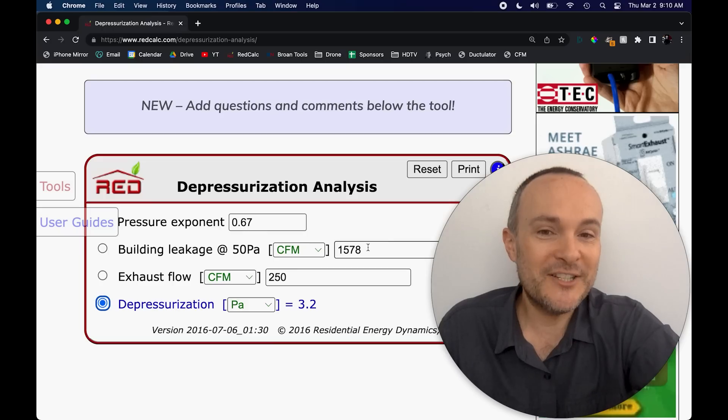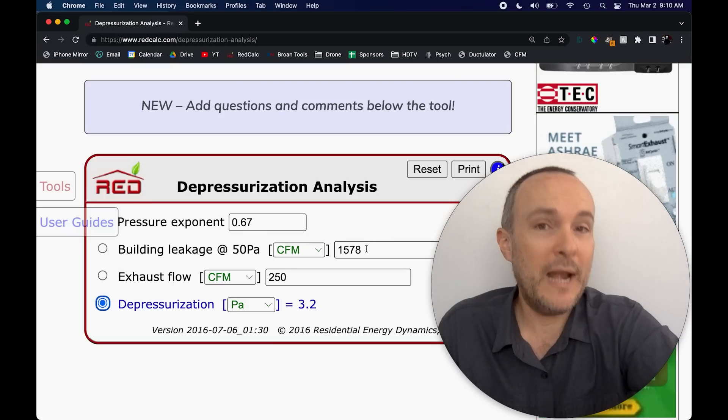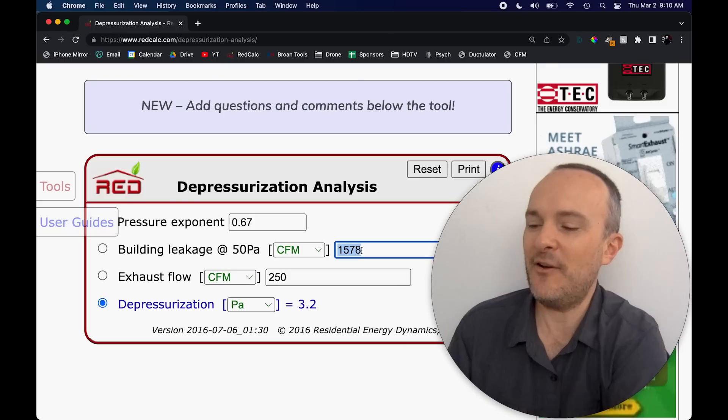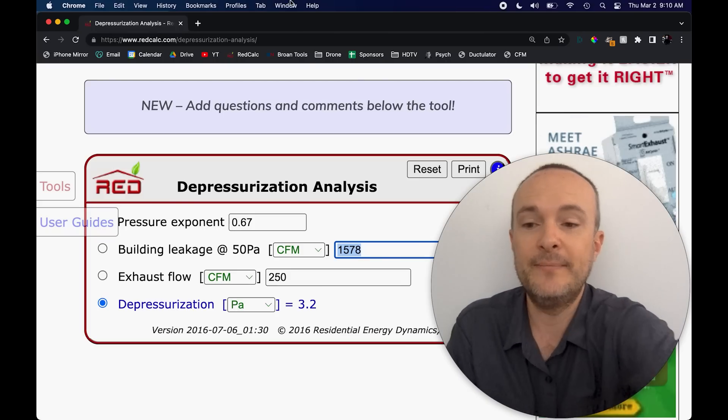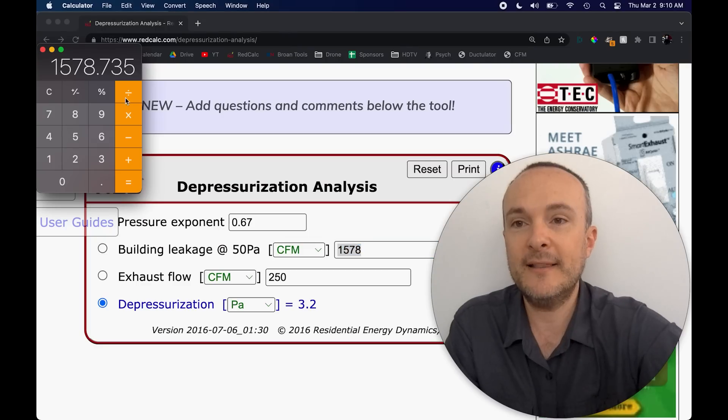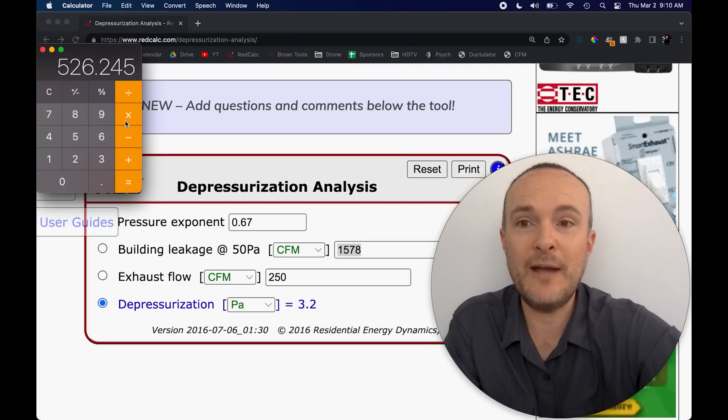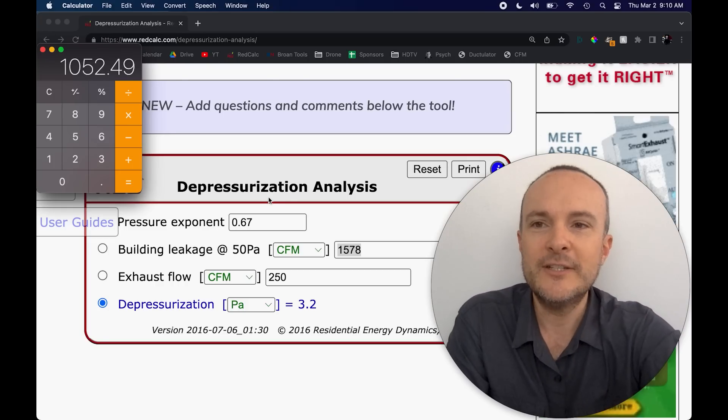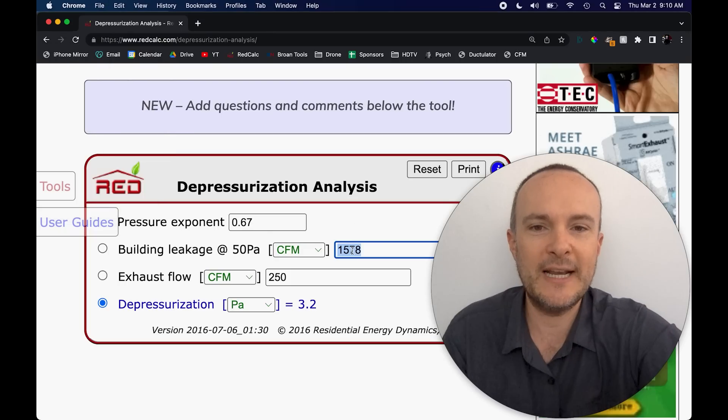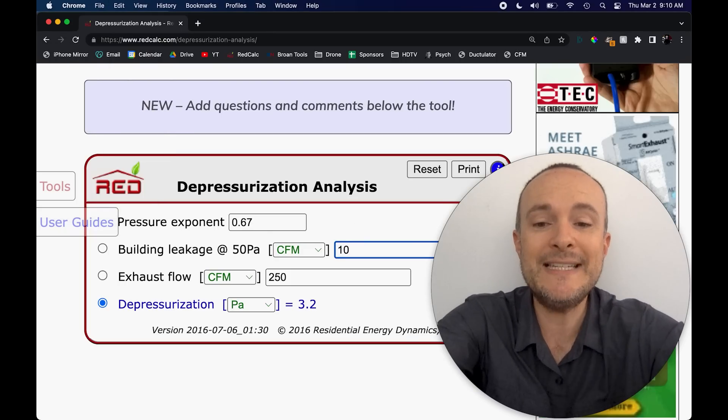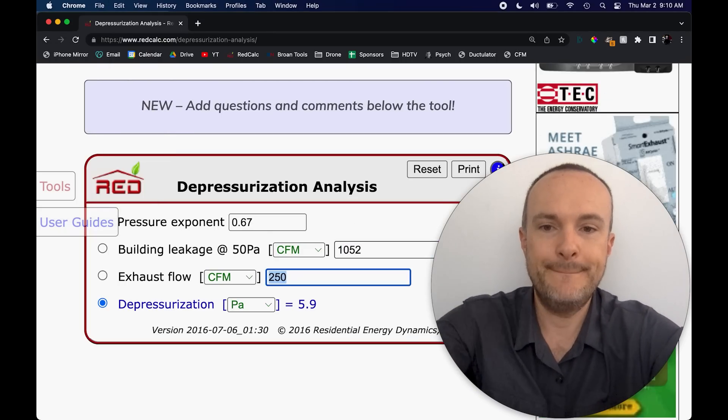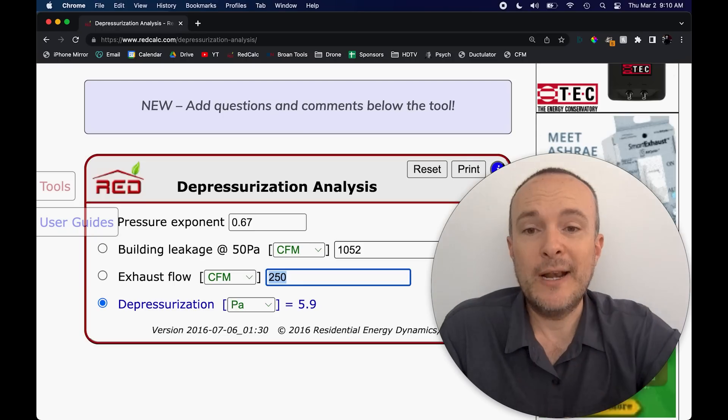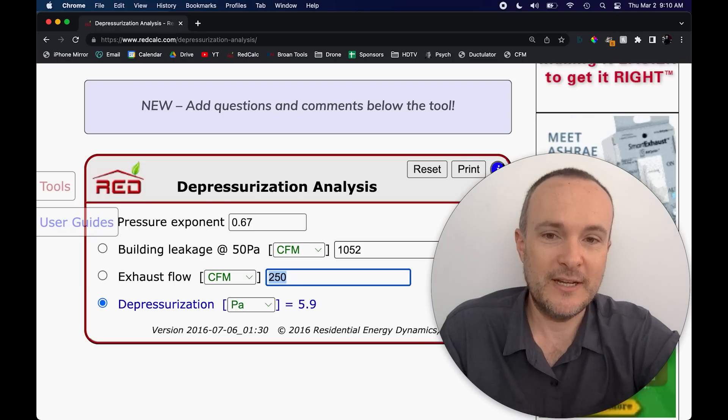Here's what we need to start doing now is analyzing what happens when we start making this home tighter. So let's take this down to two air changes per hour instead of three. We're going to go back to our calculator, take back out the three, get back to our one, and now we're going to multiply by two. There are other ways to do math, I know. So 1052 is what we're looking at now. This is two ACH 50.